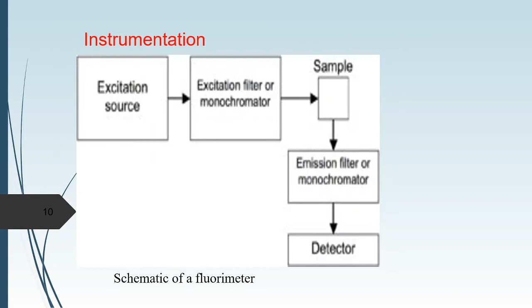Next is the instrument, the fluorimeter. The basic instrument contains the excitation source. Excitation source includes various lamps like deuterium lamp and hydrogen discharge lamp. You can use a different type of lamp as an excitation source. In a filter or monochromator, a prism or various types of glass are available to convert polychromatic light into monochromatic light.